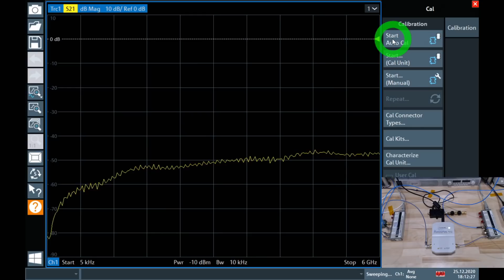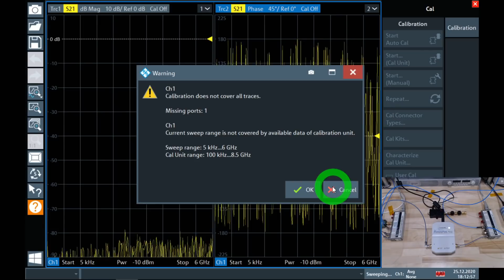It means that the electronic calibration unit is detecting that there is no power coming from port 1 of the instrument. This is a very, very handy error to get because it tells me that the microwave switches are misconfigured and port 1 isn't actually being routed to the calibration unit. This is a very good function here. The second one is that the frequency range is out of the range of the electronic calibration unit as well. That one's an easy one to fix. Okay, so let's go ahead and fix those things.